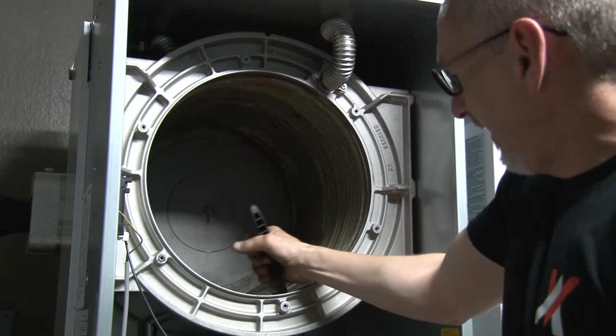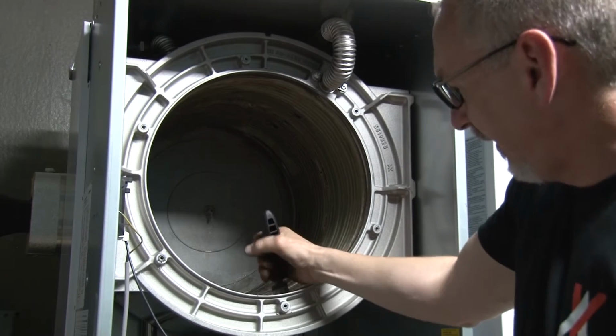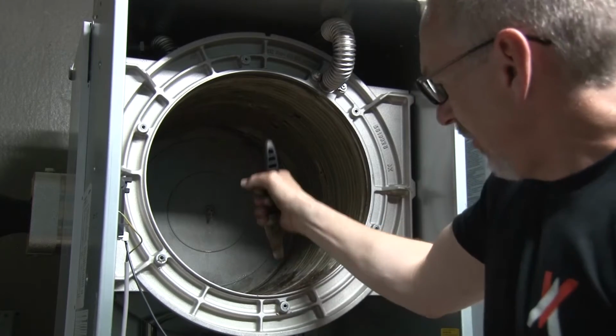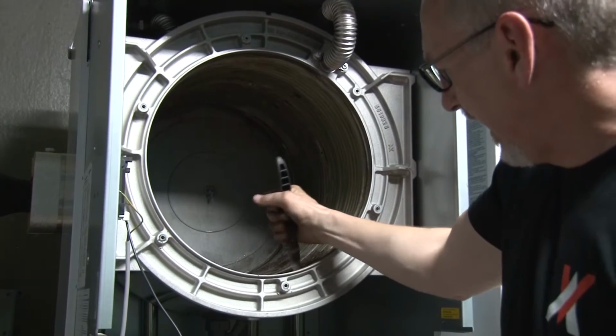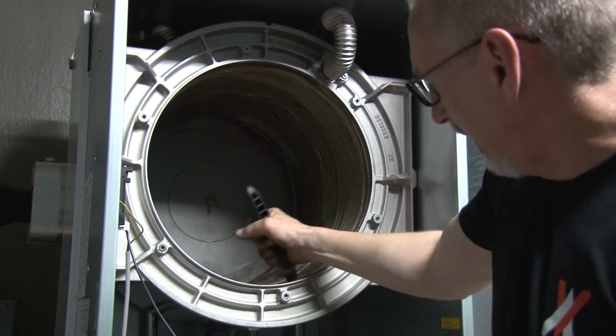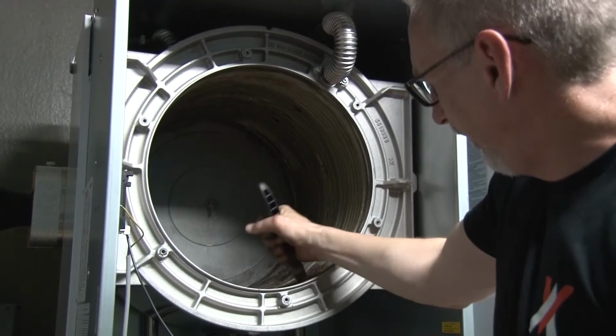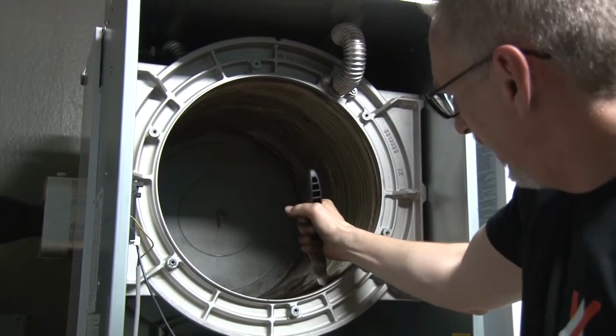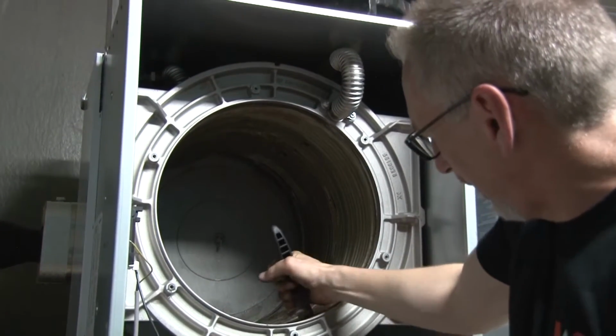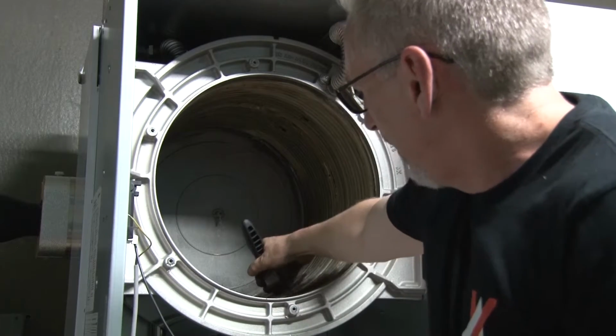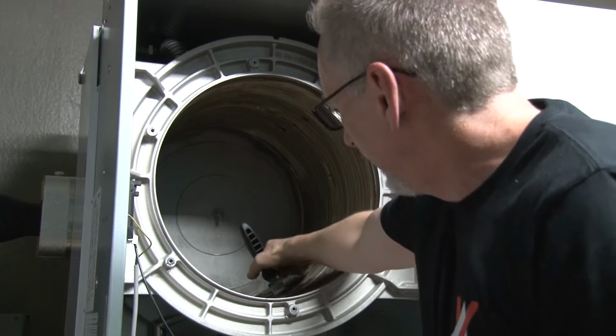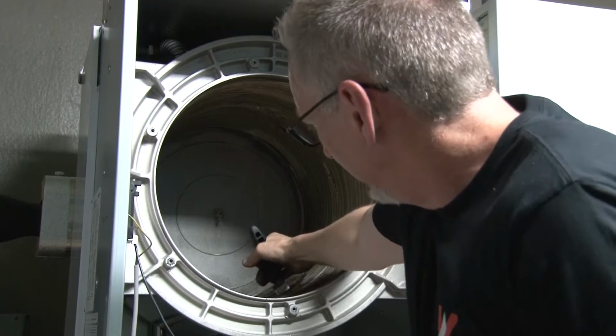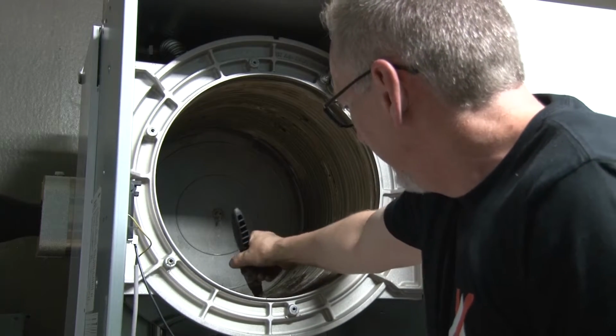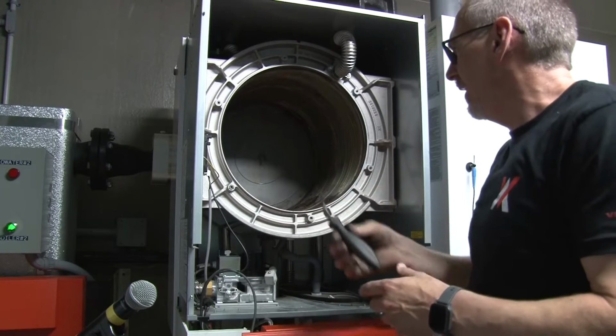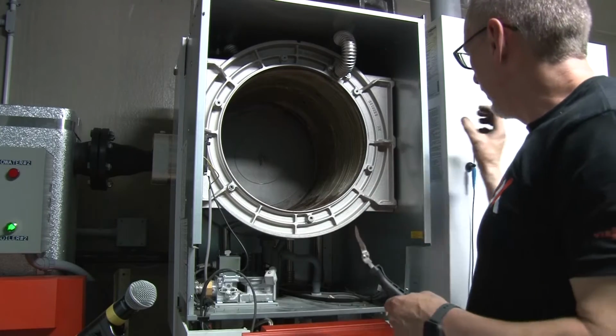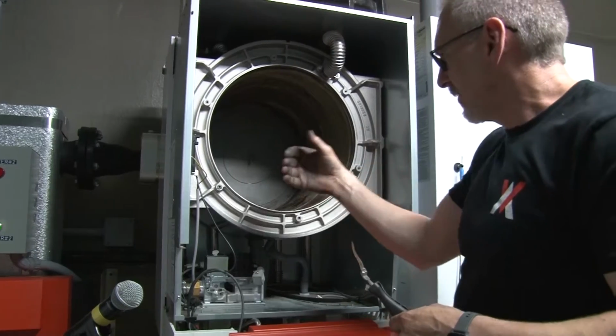So you can see how dirty that is inside of there. If I didn't get that with the knife, you're not going to wash that out very easily. You need to have the assistance of that force here to get that stuff basically cleaned out. So I'll do a couple of sections here as we move through. Get that one a little bit more. There we go. Some are going to be a little bit more dirty than others, depending on where the buildup was. Now, as I've cleaned this, we did this one here already yesterday, it went right from front to back. So I'd want to do that front to back.